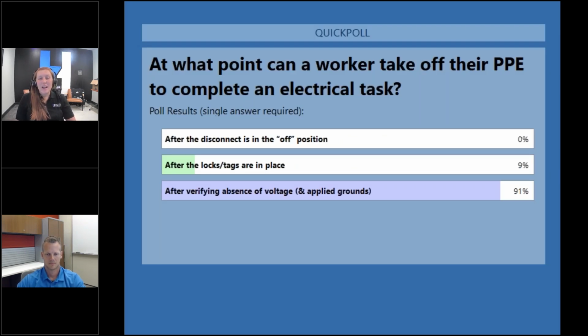You have to verify absence of voltage and apply grounds if necessary before you can take off your PPE and get to work. Just because locks and tags are in place does not necessarily mean that it is safe to work on. You have to verify that it's off with your meter. That is the key pivotal factor.